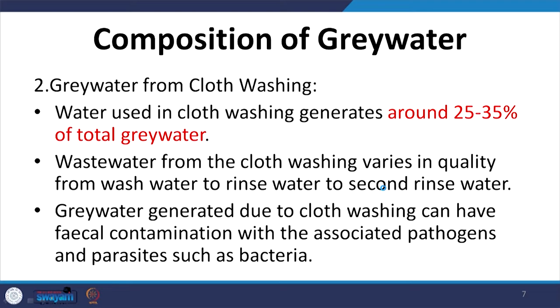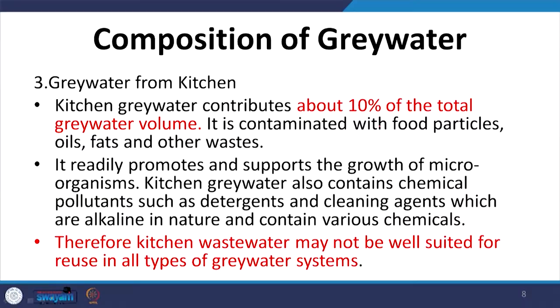Grey water from washing clothes constitutes around 25 to 35 percent of the total grey water generated, and again it contains a substantial amount of chemical contaminants because of the presence of detergents and soaps. Grey water from kitchens accounts for around 10 percent of total grey water volume and is contaminated with food particles — organic waste — as well as oils and fats, for which special traps like a grease trap may be required, along with some small quantities of chemical pollutants.